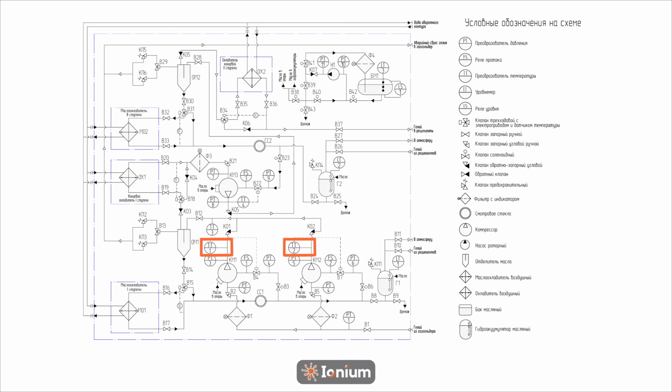The oil flow rate is gauged by the helium's temperature. This is measured at the output instruments TT1 and TT2 from compressors KM1 and KM2. This flow is controlled by regulators at positions B4 and B7. A side glass in the oil circuit allows for monitoring foam intensity, in addition to the integrated oil injection system.